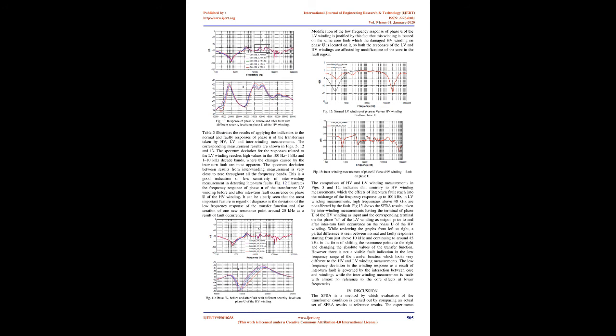As indicated in Table 4 and Figs 9-11, it should be noted that the faults with resistance values of 0, 2, 4.4, and 6.8 cause a differential current of only 11.5%, 1.56%, 0.85%, and 0.59% of rated current respectively under full load conditions of the transformer, which makes detection of these faults by traditional transformer protection devices a very challenging task.